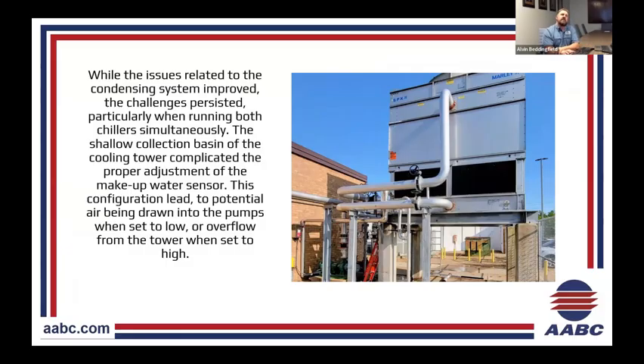Unfortunately, we still constantly were having a little bit of air enter the system. While this system improved, we were able to run the new chiller, we were able to run the existing chiller. But once both chillers came online, we started running into a similar issue. We started still pulling a little air into the system.